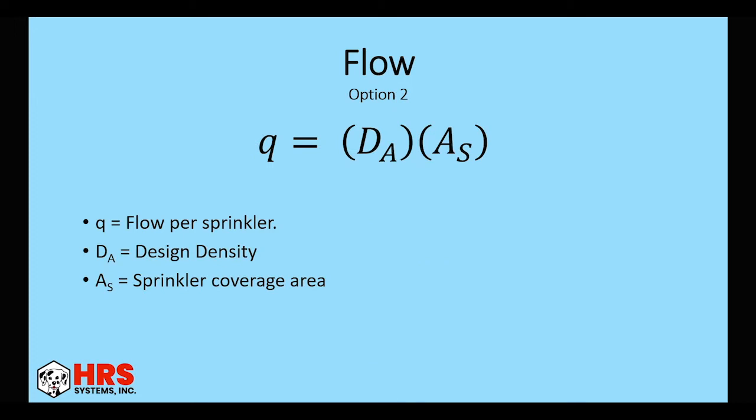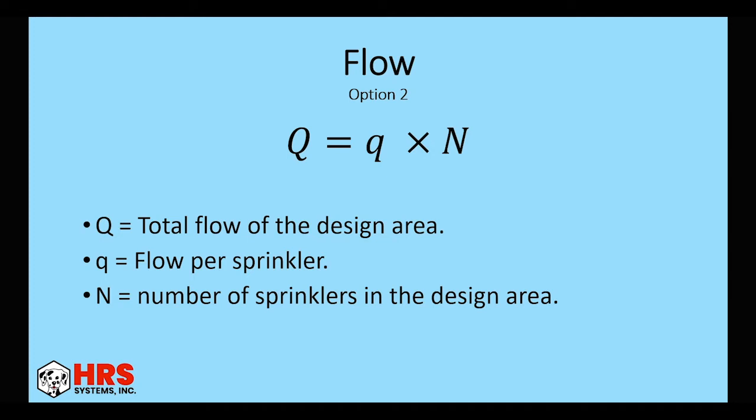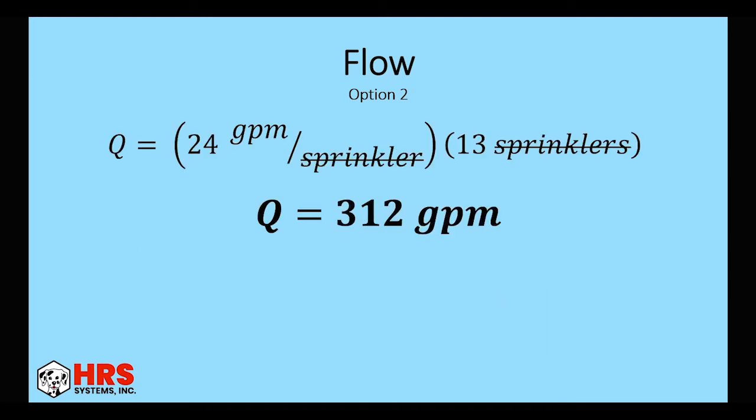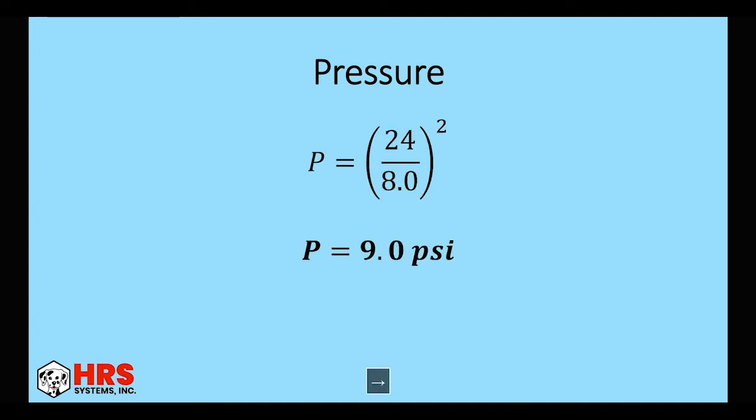The other way to do this is to get the individual flow per sprinkler. So that's the design density times the coverage area. So 0.2 times the 120 square feet gives us 24 GPM. And we know how many sprinklers we have. So we can multiply that flow times the number of sprinklers to get the overall flow. So 24 GPM times 13 sprinklers, 312. So that gives us a little bit better estimate. It's going to be higher as well. Obviously, not much higher. But to me, it just gives me a better estimate. It makes me feel a little bit better inside.